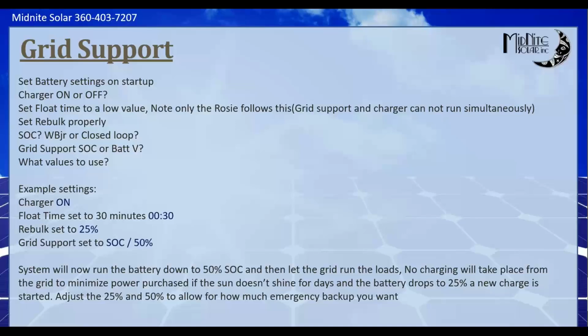I still hit 100% most days, but I can maximize that solar harvest during the day to reuse it at night. So that grid support setting, that 50% setting, or the battery voltage that correlates to it, really boils down to two things: how much room do you need in that tank every day to store the excess solar for the next night, and how much energy do you want stored in the battery in case of a power failure?